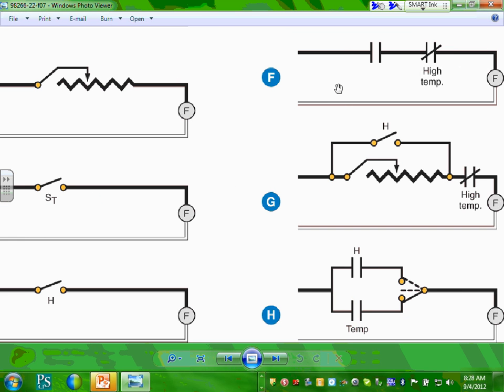F, look at F here. For F you have a high temperature sensor for the fan, so it's sensor control. G has a combination of high temperature and speed control, and H is high temperature and speed control. So temperature control, high temperature and speed control. If you go to G, it gives you a lot of other options. H has a humidistat and thermostat, temperature and humidity, and a selector switch, so you can select whether you exhaust based on humidity or temperature.